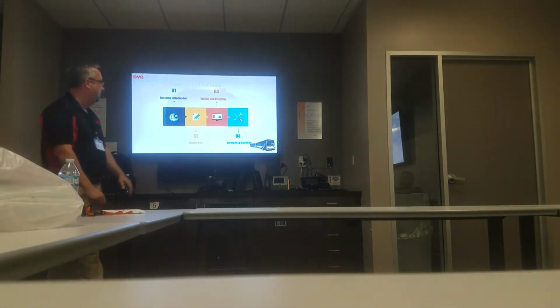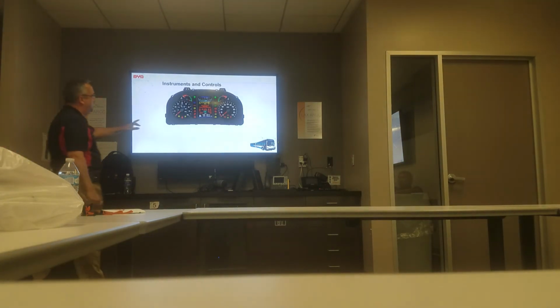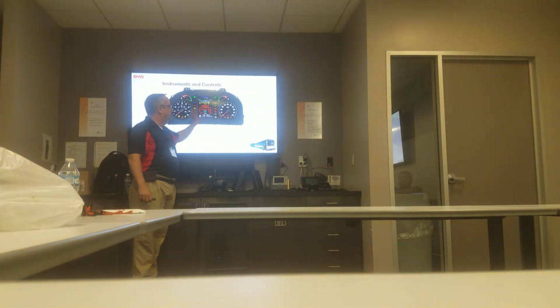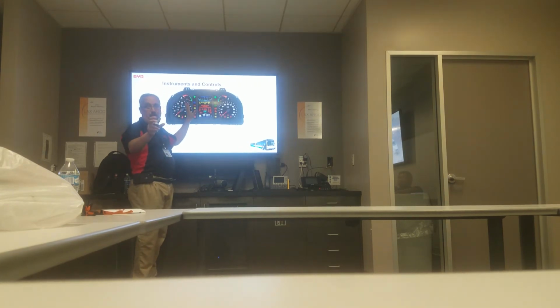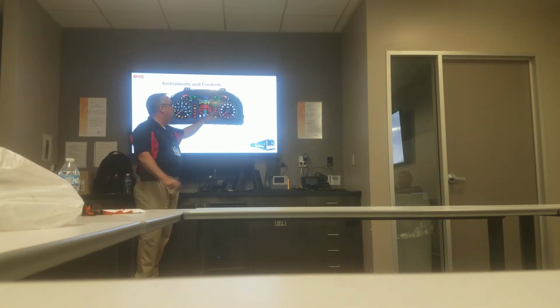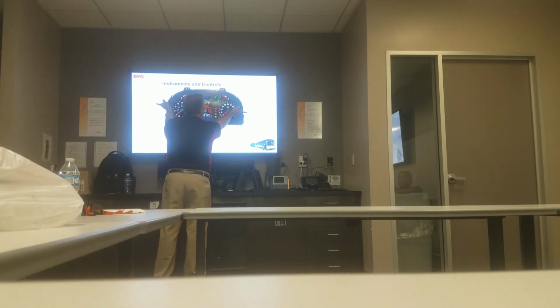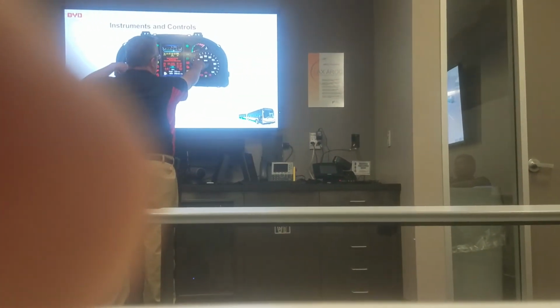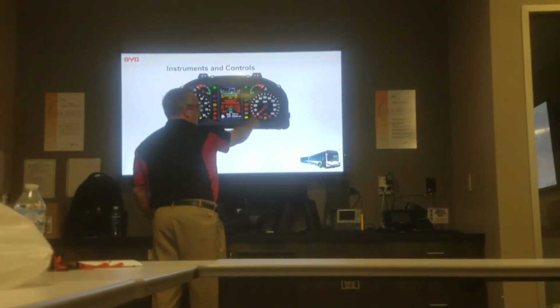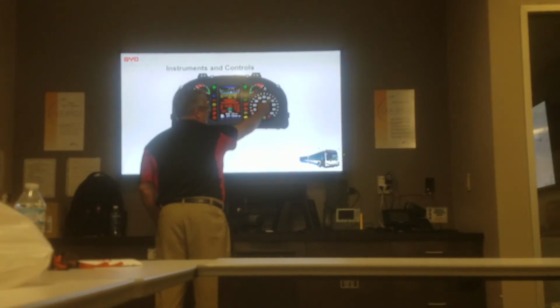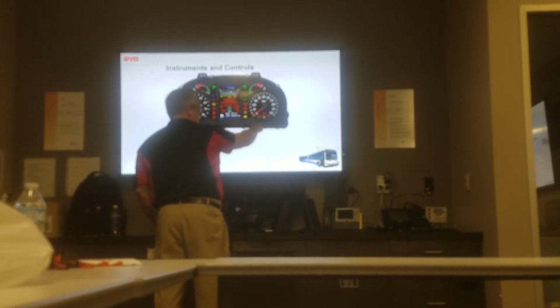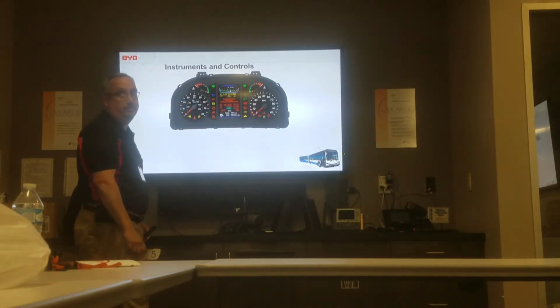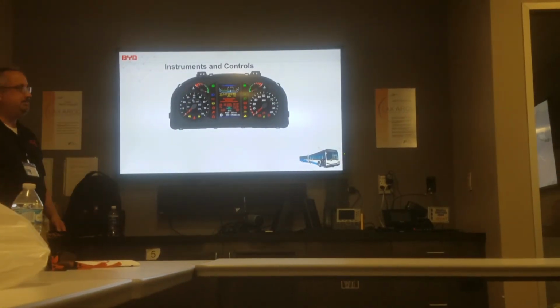The needle you're asking about is the SOC needle. Whenever you turn that master switch on, all these lights come on and all these needles calibrate. But this one, if it's out of calibration, might not go back to zero, it might stay over here when you turn it off. So when you first turn it on, it'll come down some and then go back up. It needs to come all the way to zero before it goes up to wherever the SOC is. Does that make sense? Yeah.